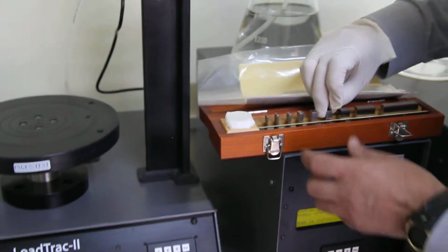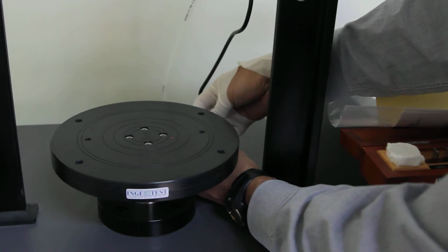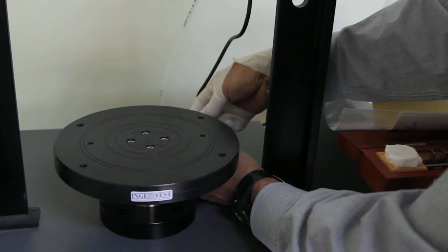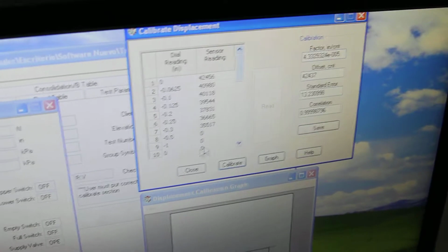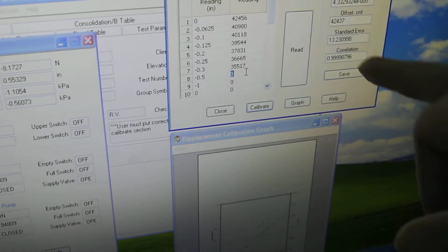While I'm doing this calibration, I want to make sure that there's no one bad point or that something is not right, and I could tell in the graph if a point is completely off or the error is too big on each point. What you see here, so we have my next point, and I'm keeping track that my correlation has to be at least 4 nines and my standard error as low as possible.